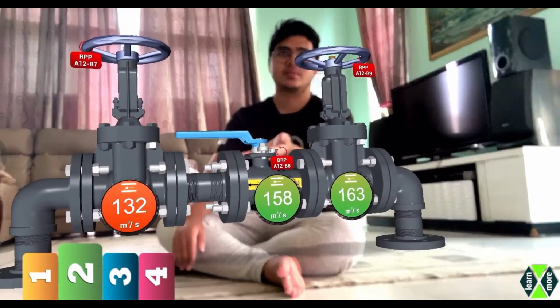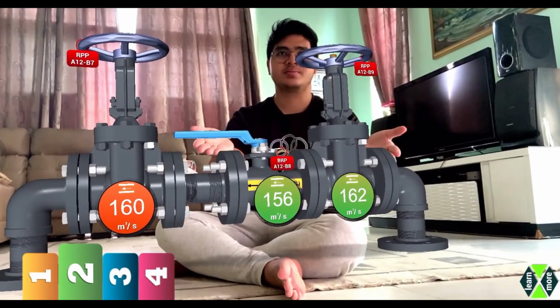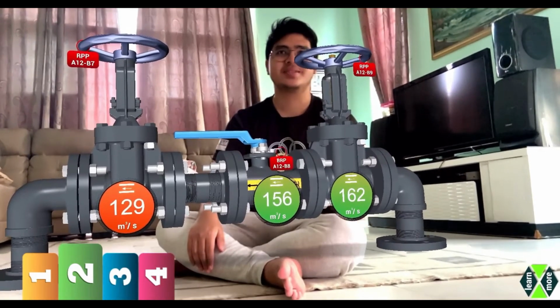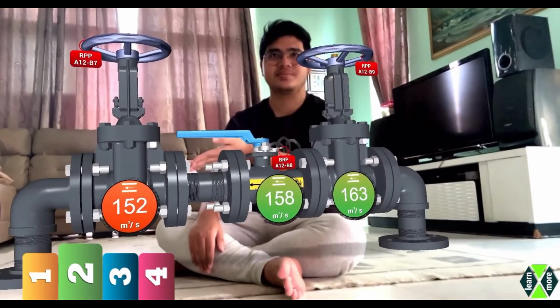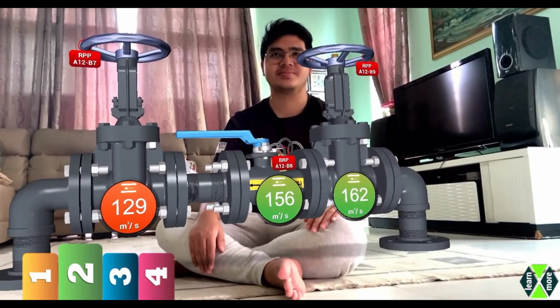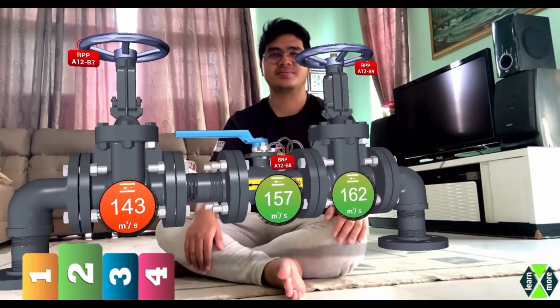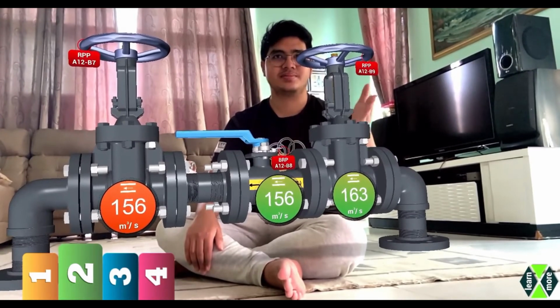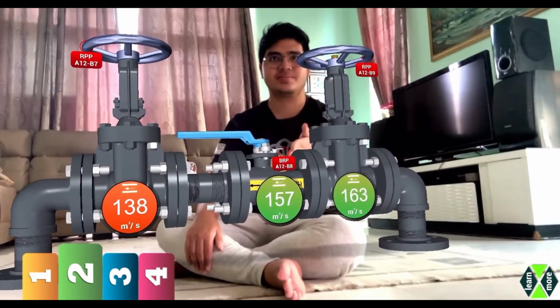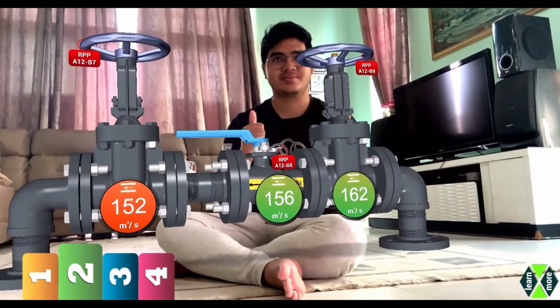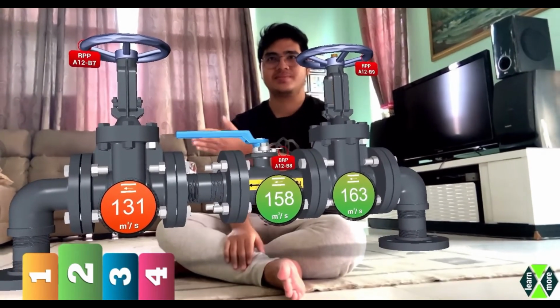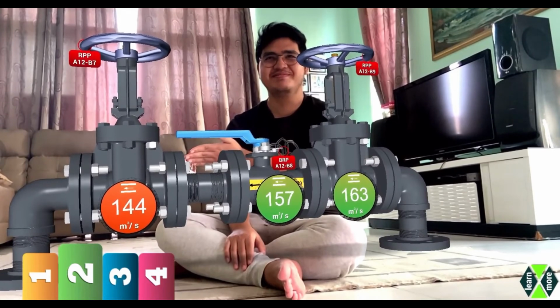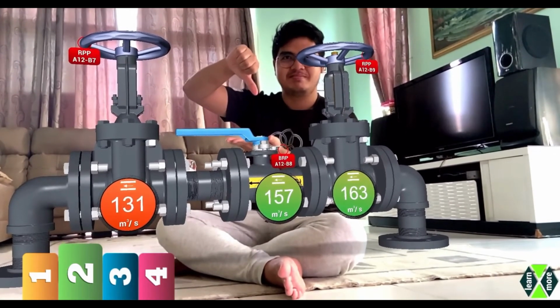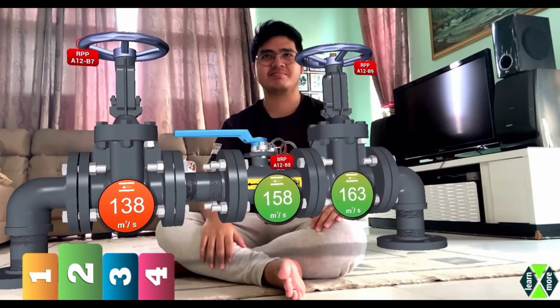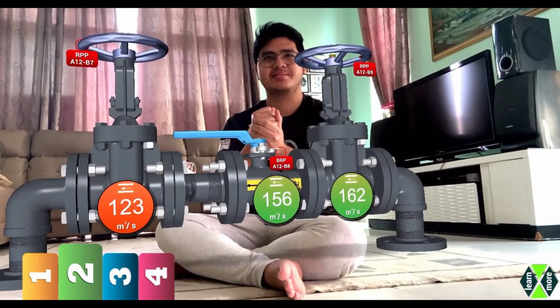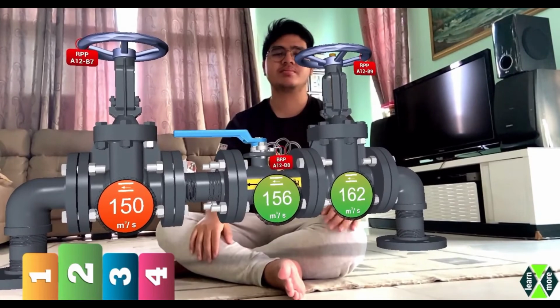An alert has been raised. Fluctuation has been detected at valve location RPP A12B7. Let's analyze the readings from the waste liquid valve. As we can see here, at valves B9 and B8, the reading is quite stable, while at valve B7, the pressure reading is erratic. So we know one of the valves is problematic and we need to repair the failure.